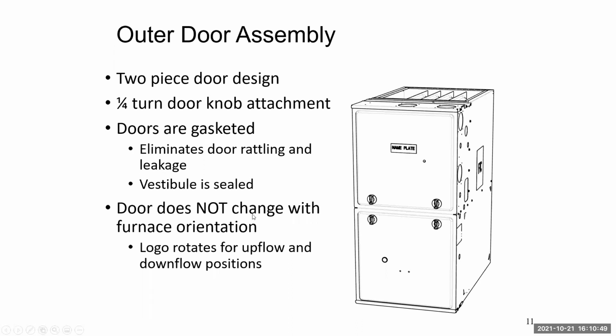Just some of the basics of these units. They've got the quarter turn knobs on them still. Doors are gasketed. I know from experience being out in the field for so long, it's real easy, if that gasket's dangling, hanging off, to just rip it, throw it, get it out of your way and move on. Don't do that unless you want a 3 o'clock in the morning call back for a noise complaint, and you're going to get there and it's just going to be because of that door gasket being gone. If you don't have the gasket, get some foam tape off your truck, make your own. Does the same exact thing. But leave it on there or repair it, replace it, whatever needs to be done.